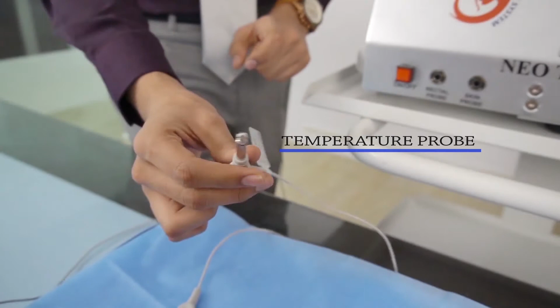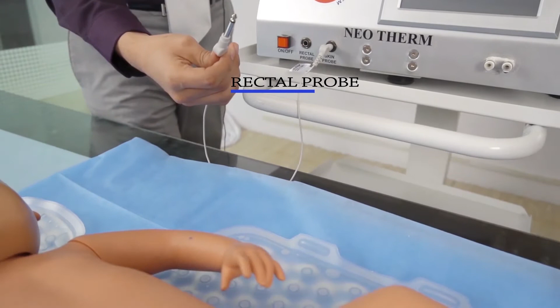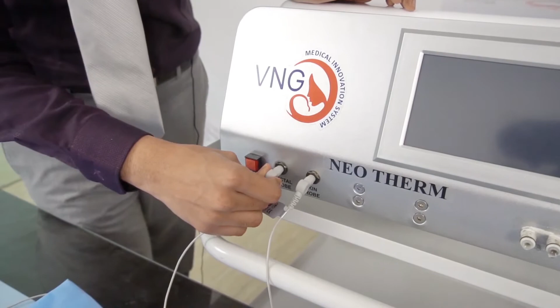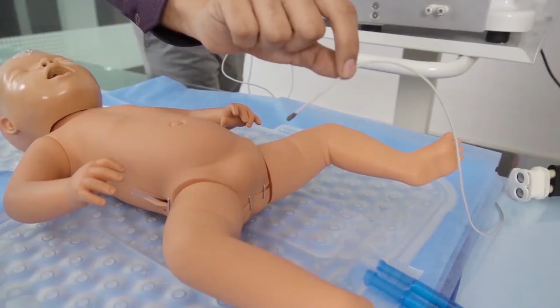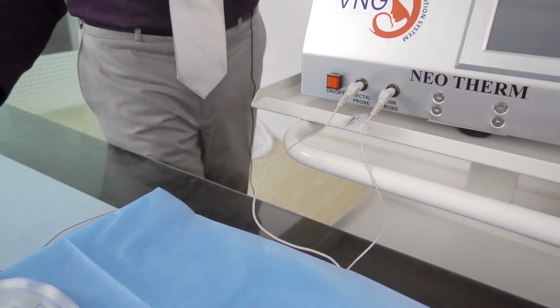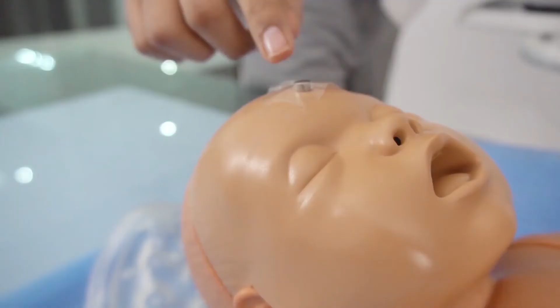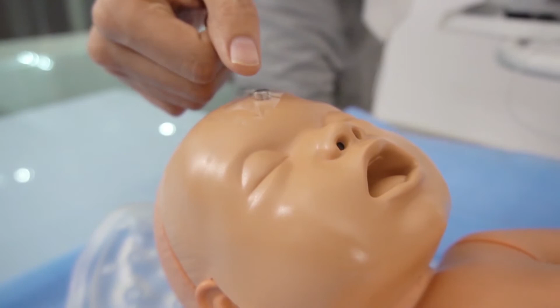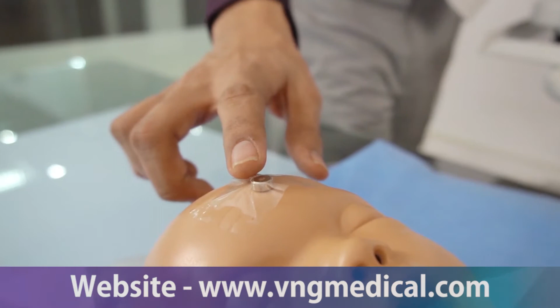This right here is the temperature probe. The temperature probe will be plugged into the skin probe terminal, and this here is the rectal probe, which will be plugged into the terminal of the rectal probe. The rectal probe will be inserted from 3 to 5 centimeters in the rectum of the baby. Next, the skin temperature probe can be placed anywhere on the skin of the baby. It can either be connected here or at any other part, the arms or the stomach of the baby. The skin probe is only used for a referral temperature, but the device is mainly controlled by the rectal probe only.